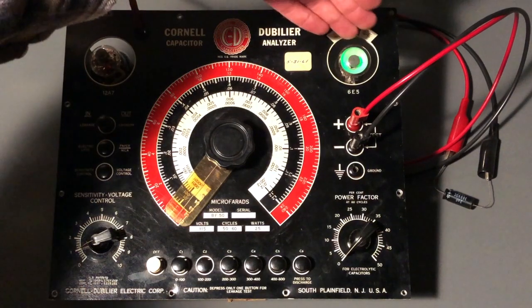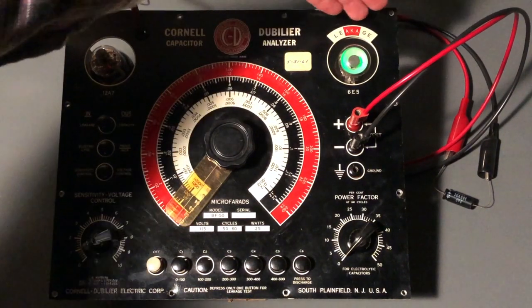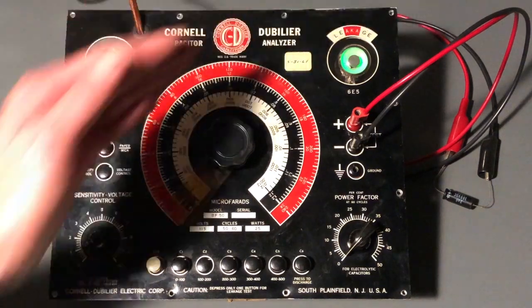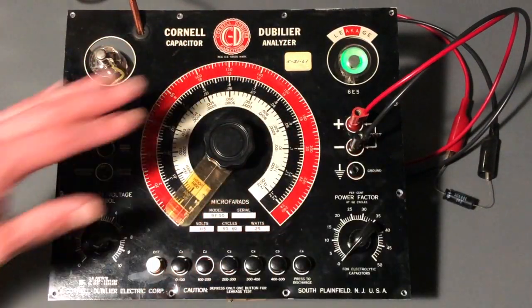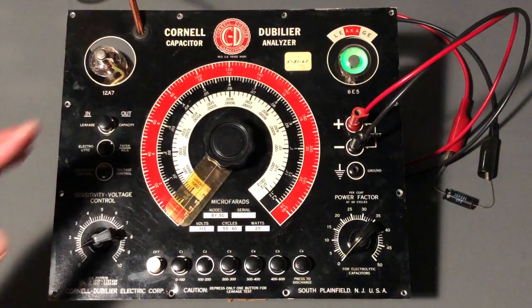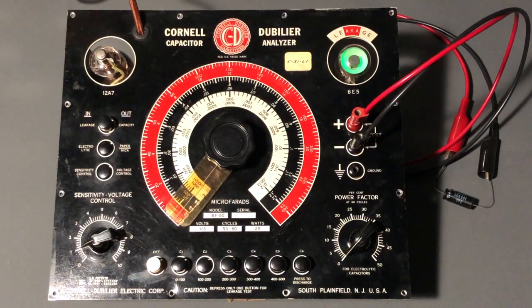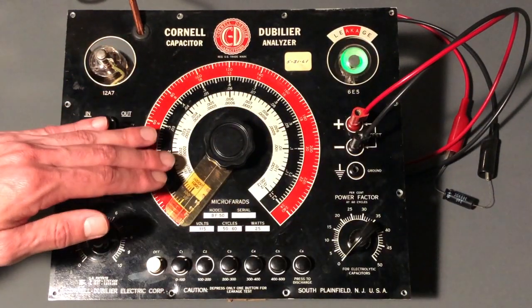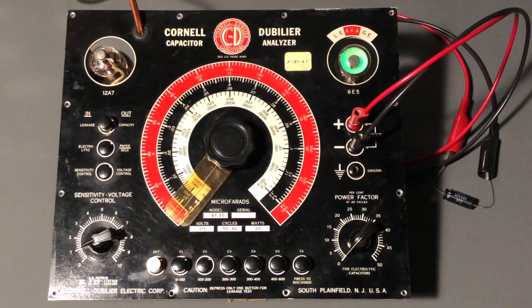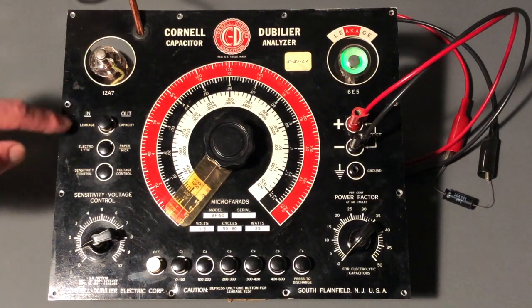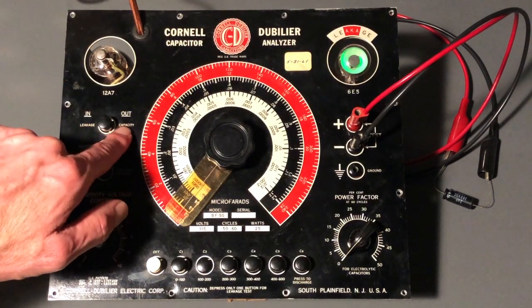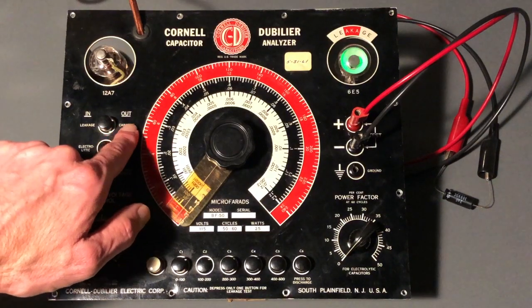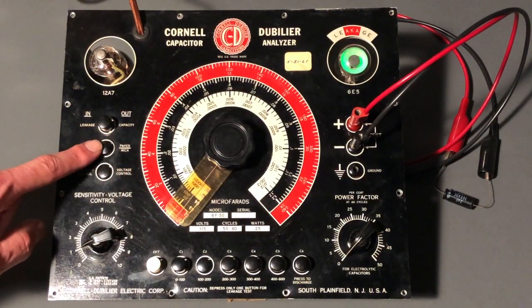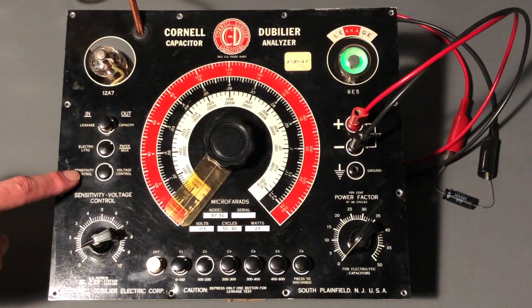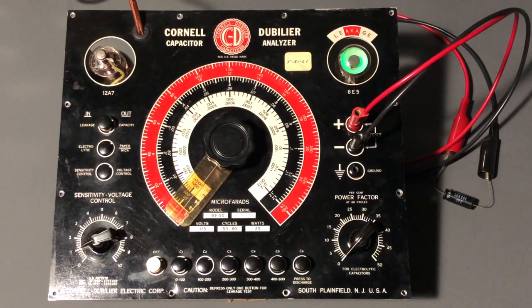So we'll want to watch the eye tube up here. The leakage label up here no longer applies because the eye tube will be opening and closing as we rotate this control, and that will show the balance on that bridge circuit. So when the eye is completely open at a maximum opening, that's when the reading is taken for the value of the capacitor. So over here on the switches, we have the leakage capacity test in the out, so it's in capacity. Electrolytic, this is in the in position, and this is in the in position for the sensitivity control, which is this control down here.